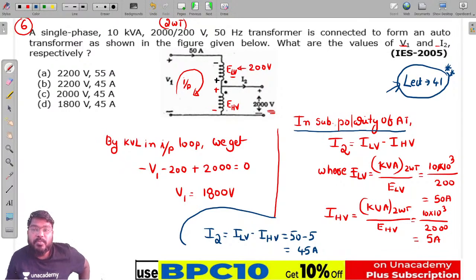So yes, it's additive polarity, subtractive polarity. Subtractive polarity means LV winding and HV winding of the two winding transformers are connected in series in such a way that the fluxes produced by these two windings are in the opposite direction. So therefore the net voltage is the difference, here 2000 minus 200, you can answer this. So currents also are the difference of the two currents. Here, no need, by seeing this one word you can answer easily. So here supply, the net voltage is a difference, current is also different.